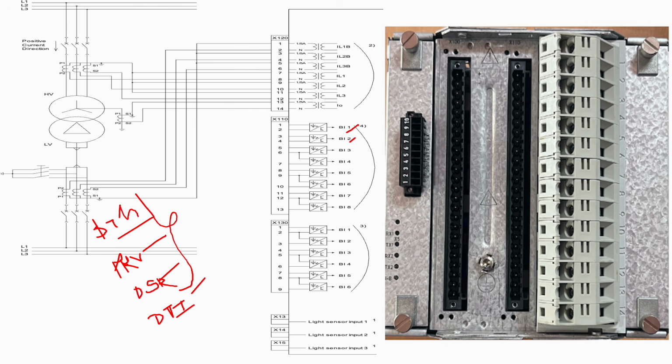Okay, because in relays, yes, in RET 615, whenever the differential relay operates, you will get full data, you will get time stamping and all. But whenever our Buchholz, PRV, OSR, these auxiliary relays operate for any reason, we are not able to get full data of that particular time, or we are not able to get time stamping.